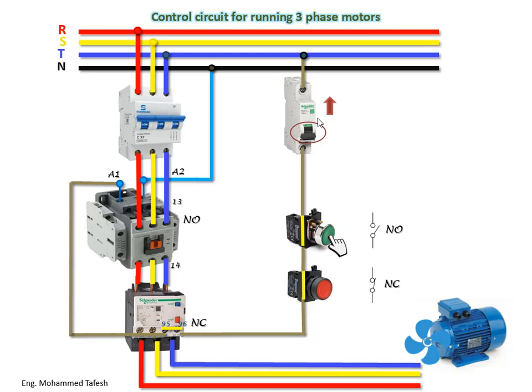The electric current will start to pass in the circuit. Since the contact points 95 and 96 of the overload are also closed, the current will continue to pass through them and into the magnetic contactor coil, causing the contactor to become magnetized and attracted inward. The main connection points of the power circuit come into contact with each other, and the auxiliary contacts 13 and 14 also close.